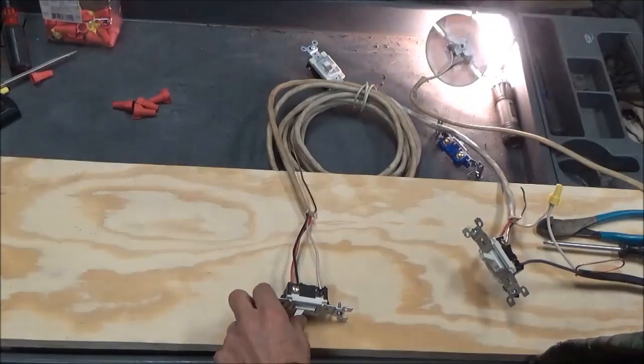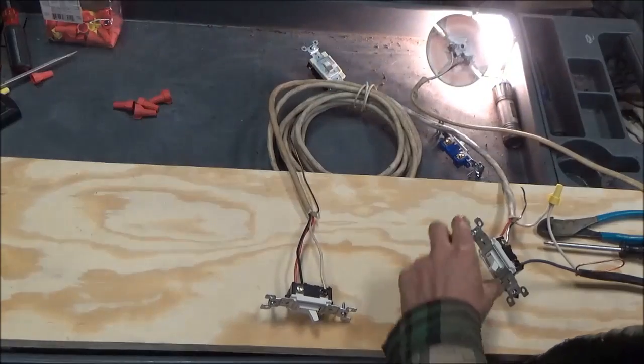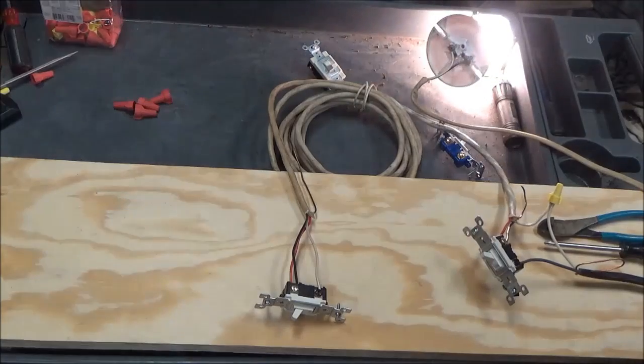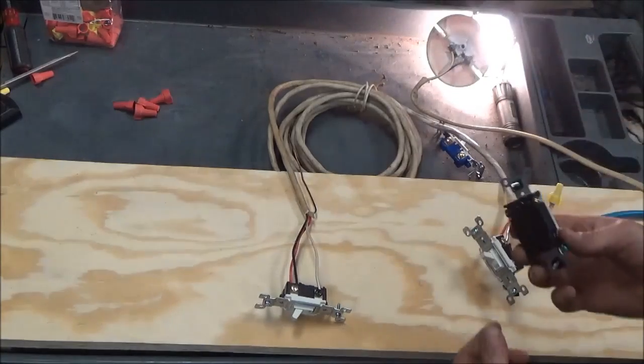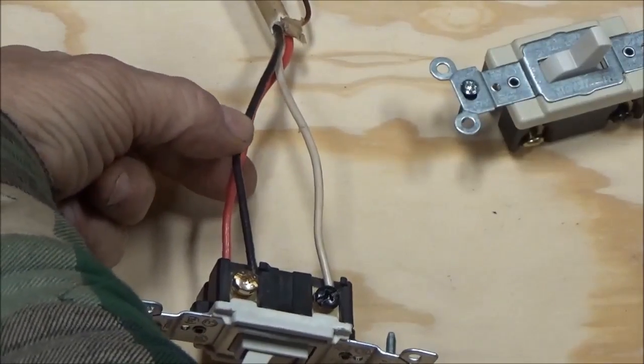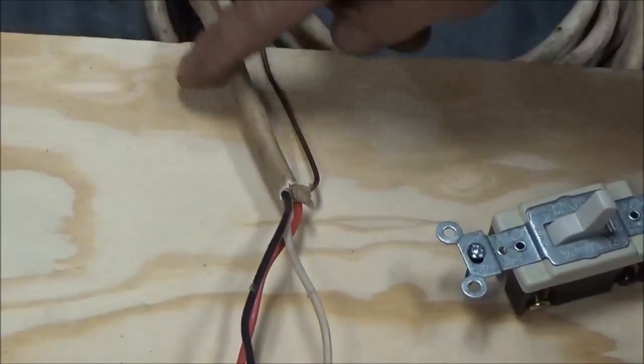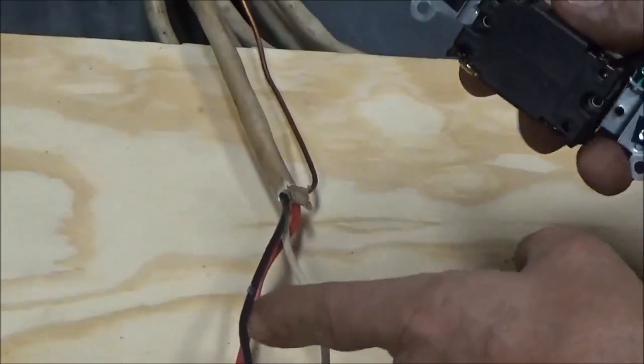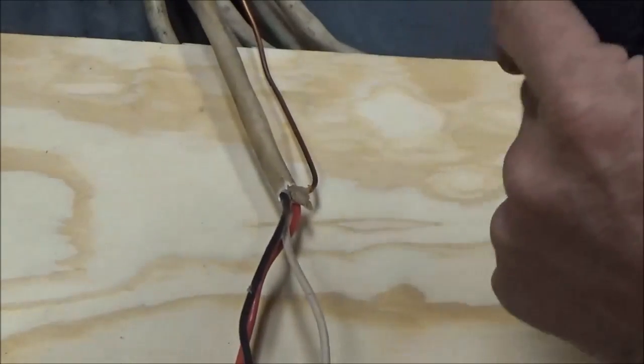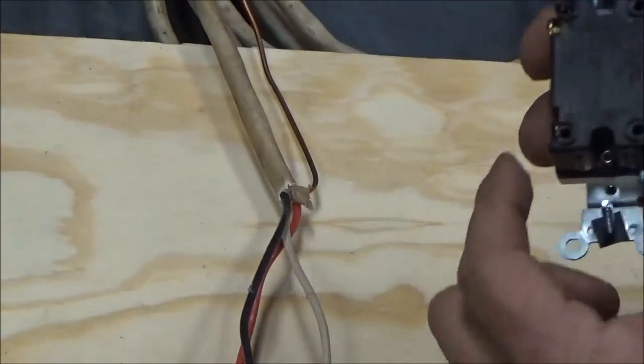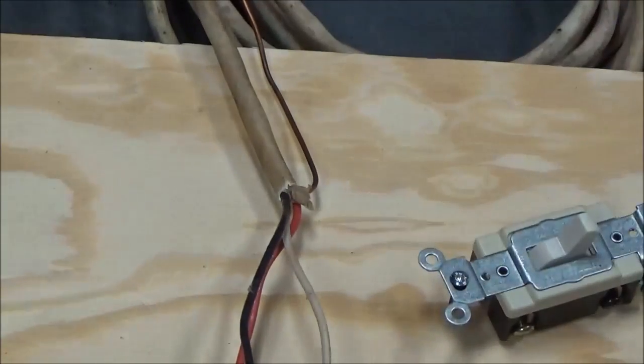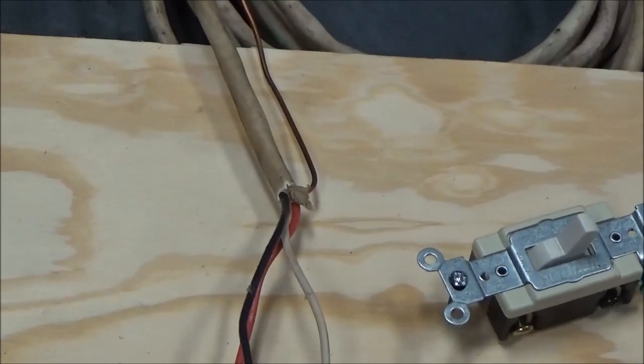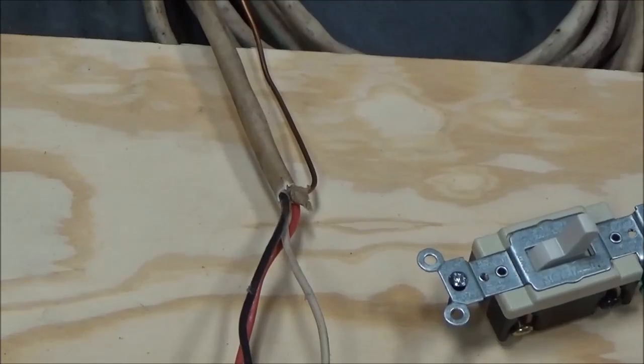So, everybody's seen those work. Now, for the four-way, we're going to cut these traveler's wires. I'm going to strip this insulation back a little bit, so I have room to cut these traveler's wires. These traveler wires, two of those, on one side go on the brass screws, and the other side goes on the black screws. And it's a very simple circuit. And then you have four wires. And then you have three switches controlling the light from three different places.